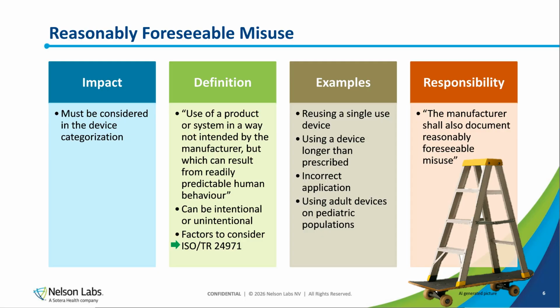So what's really the definition of the term? It's a use of a product or system in a way not intended by the manufacturer, but which can result from readily predictable human behavior. It can be intentional or unintentional, and there are additional factors to consider within ISO 24971.